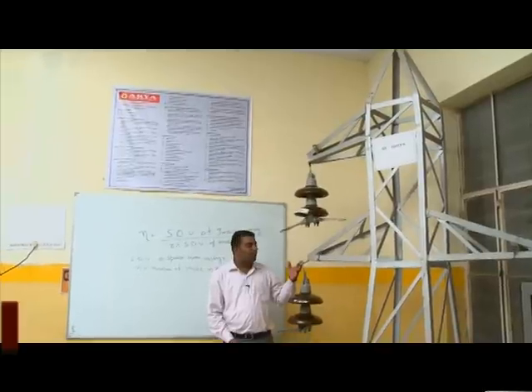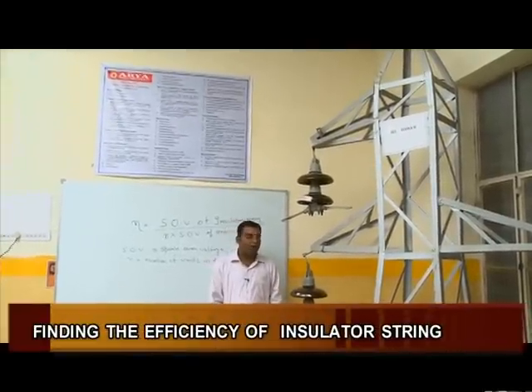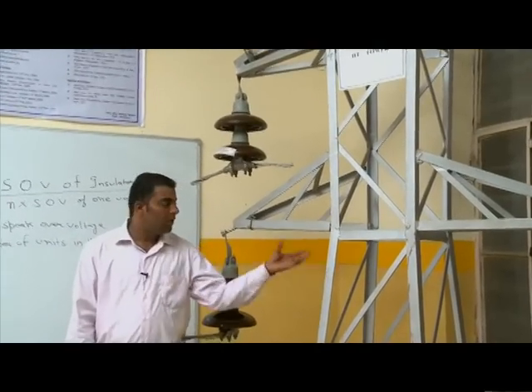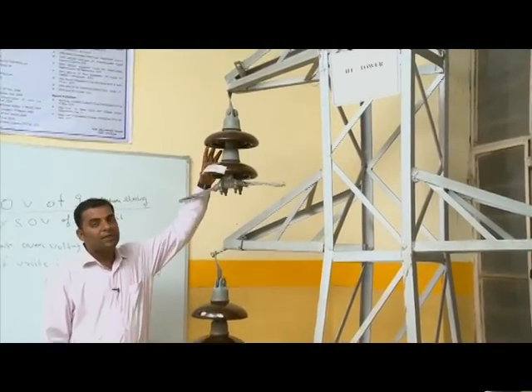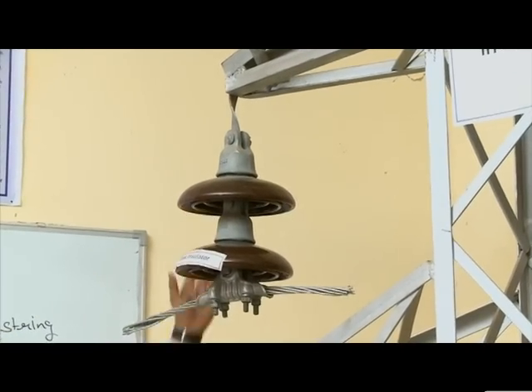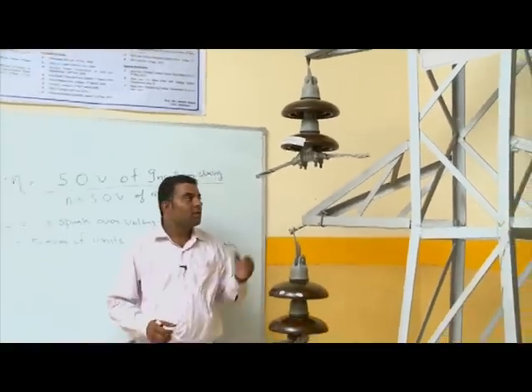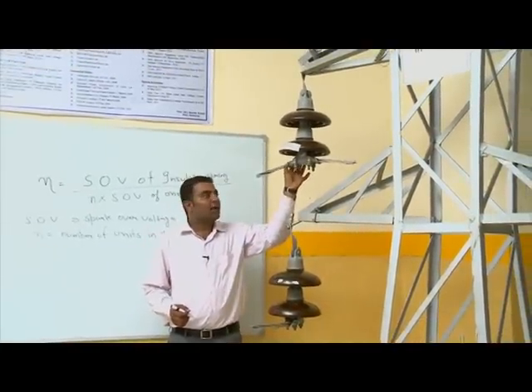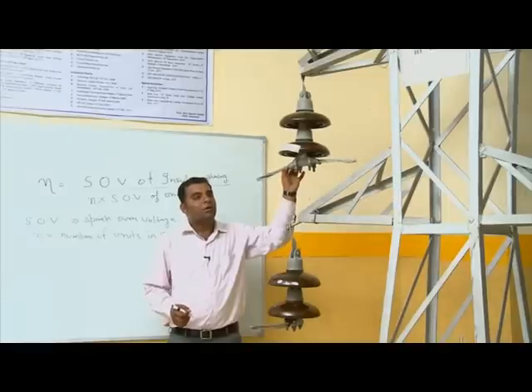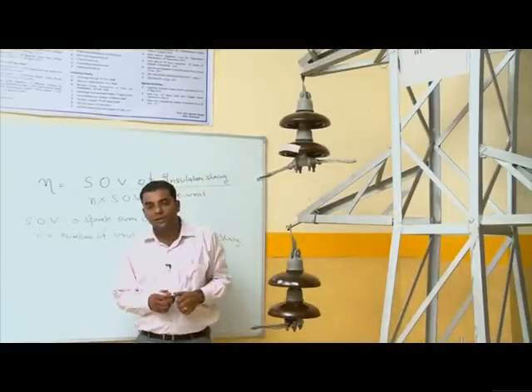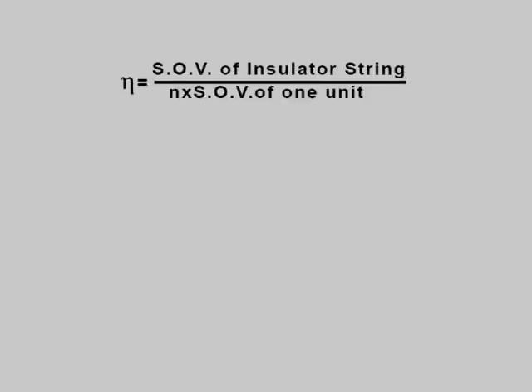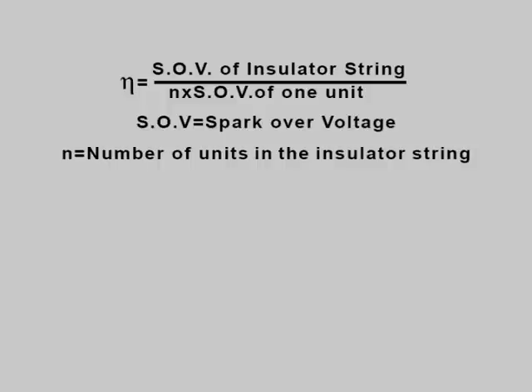It is a demonstration setup to find out the efficiency of an insulator string. In this setup, we have an HT tower, cross arms, a conductor arm, and an insulator string which hangs on the cross arm. The output of the transformer is connected to the conductor arm. For finding the efficiency of the insulator string, we use the formula eta equals SOV of insulator string upon N into SOV of one unit, where SOV represents the spark over voltage and N represents the number of units in the insulator string.